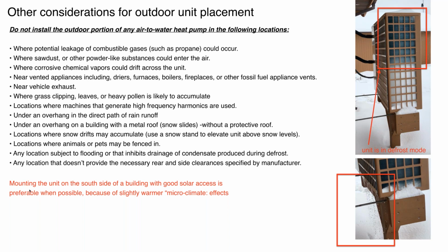If you have a wood shop and you're producing sawdust or some other type of dust, we want to keep it away from there. We want to keep it away from where vehicles would be running, again, with the water vapor coming out of the exhaust pipe. Okay. Don't put the unit directly under an overhang unless there's a gutter. And if you look really carefully at this photo in the upper right here, you can see there is a gutter across the top of that unit.